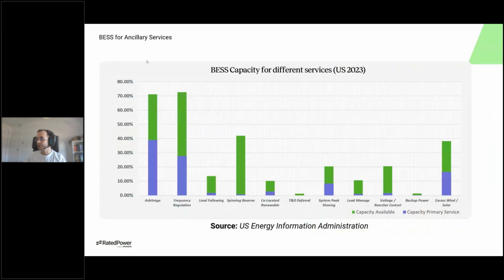And just for you to understand the usage of batteries, this is from the US from 2023. In green, you see the capacity available of all the batteries installed in this year. One battery system can provide different strategies or different services. That's why you see that if you sum all the green charts, it will go way above 100%, because you could have a system that provides arbitrage and frequency regulation. But mainly here, I want you to understand that the main two objectives of the batteries in the US right now are arbitrage and frequency regulation.